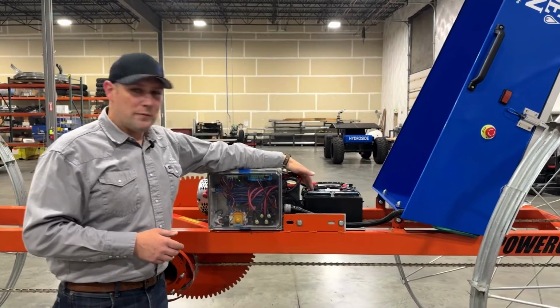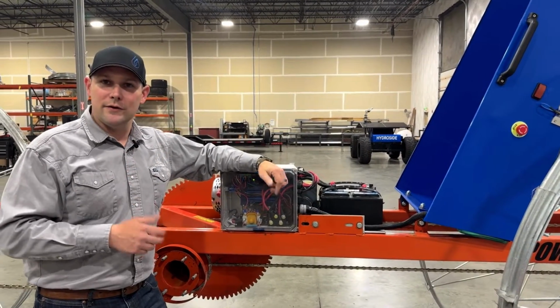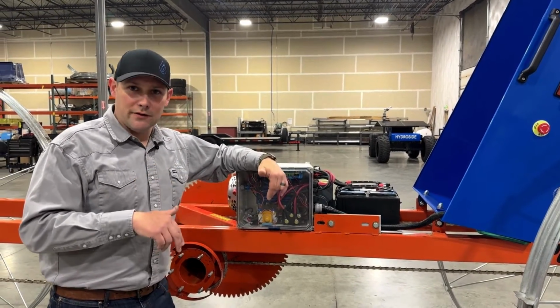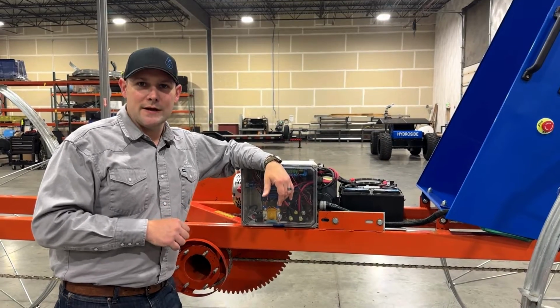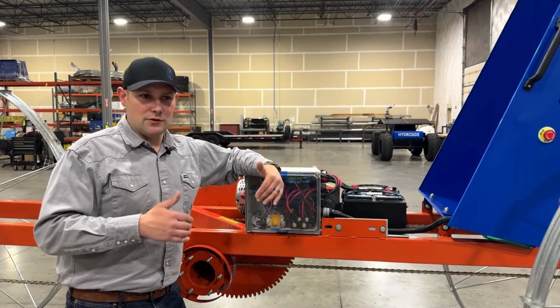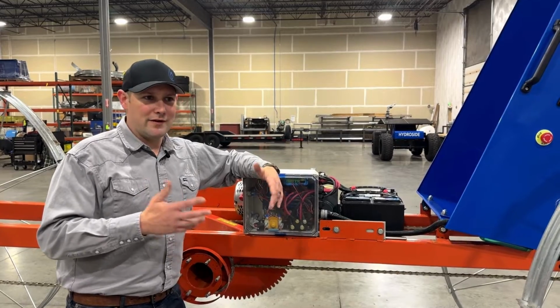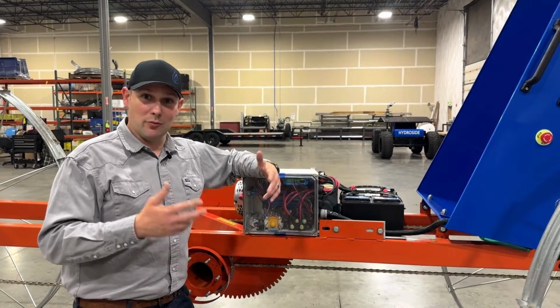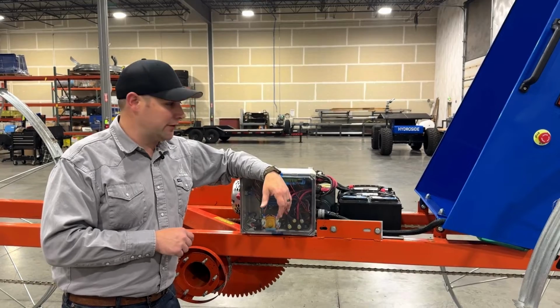Now, if you've got a voltmeter, you can go ahead and touch off on those. It's 24 volt wired in series, two 12-volt batteries in series, so you really want to see a voltage north of 24 volts. 25.8 would be considered perfectly topped up for a 24-volt system.